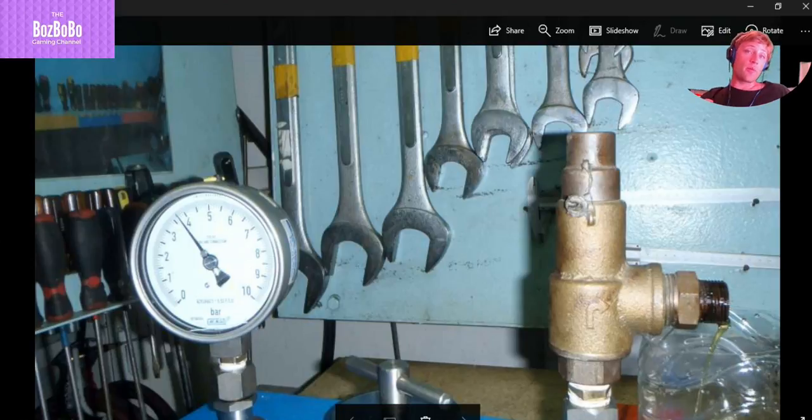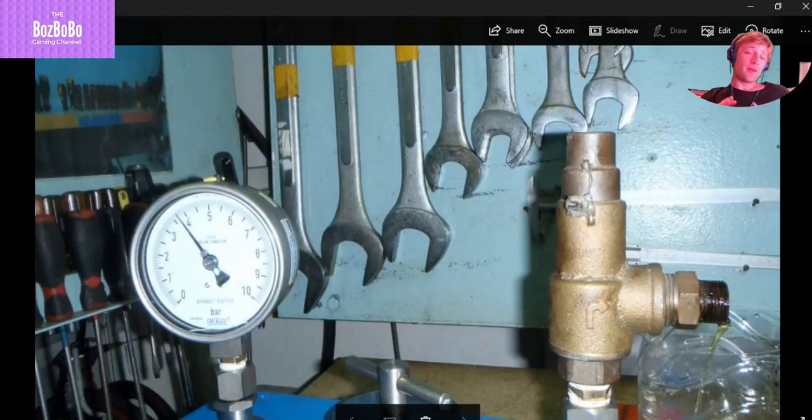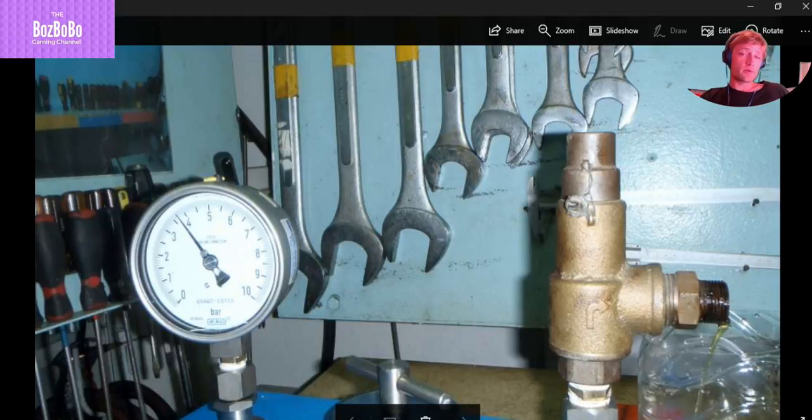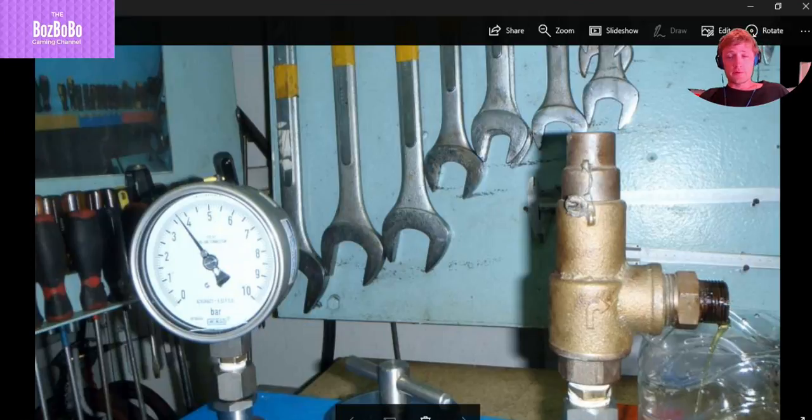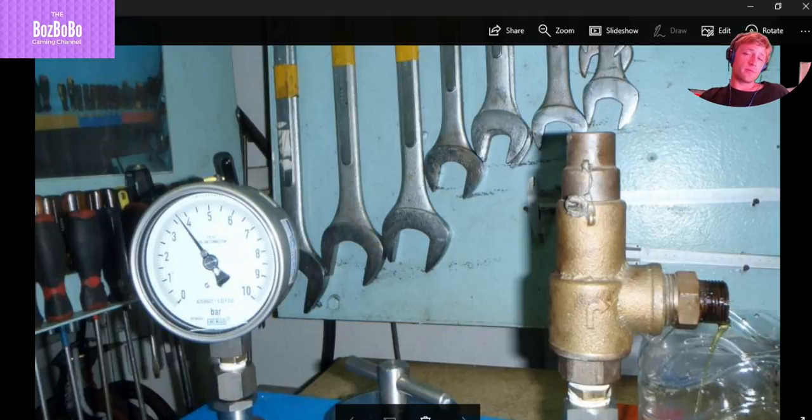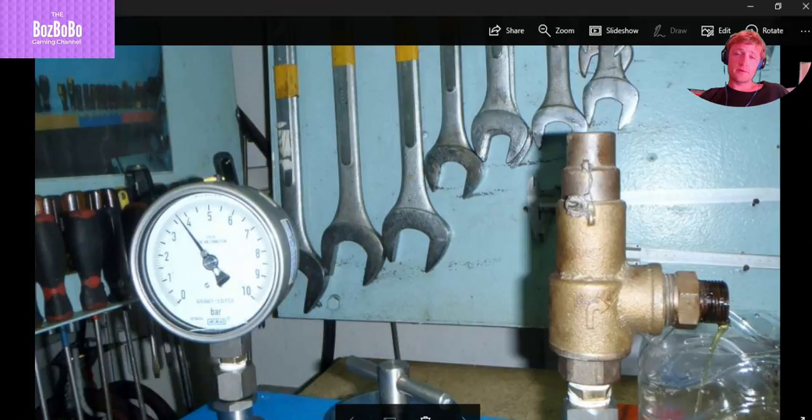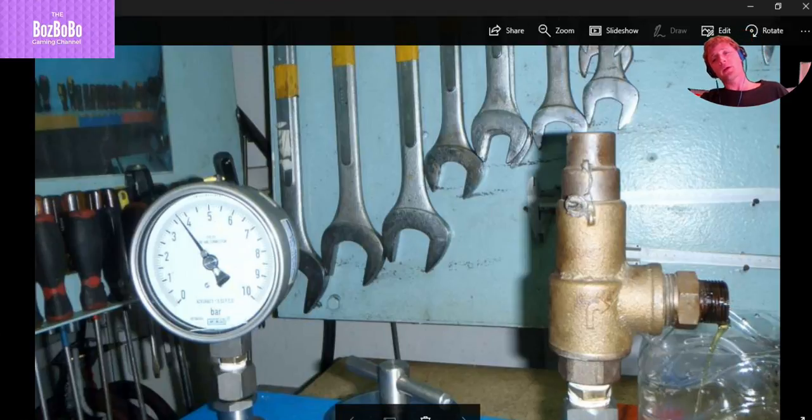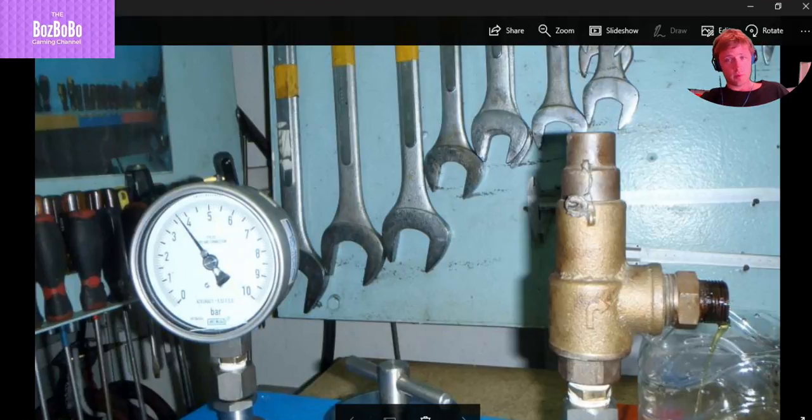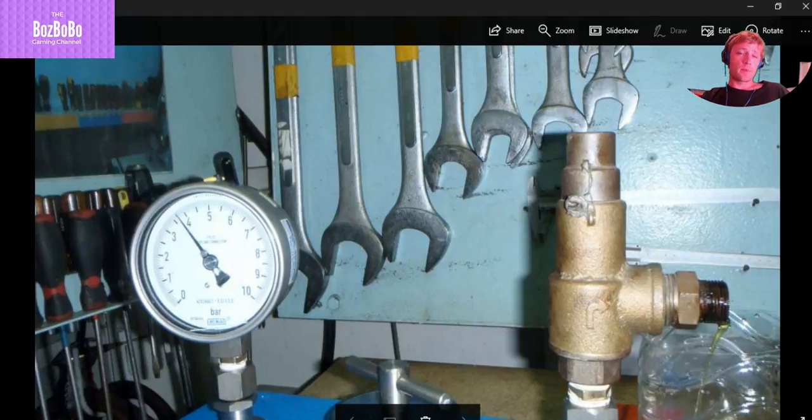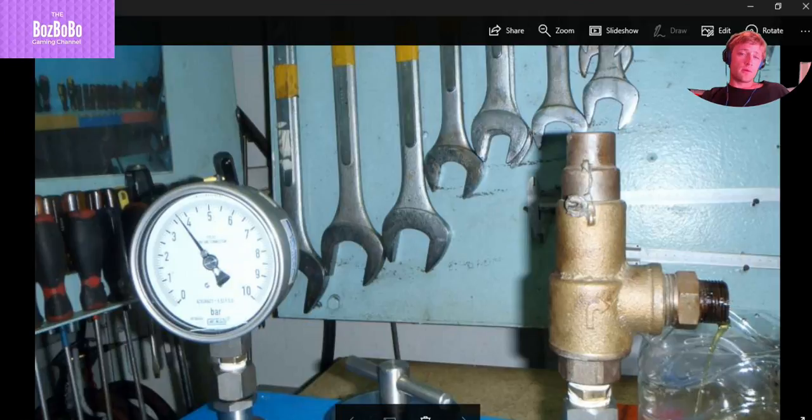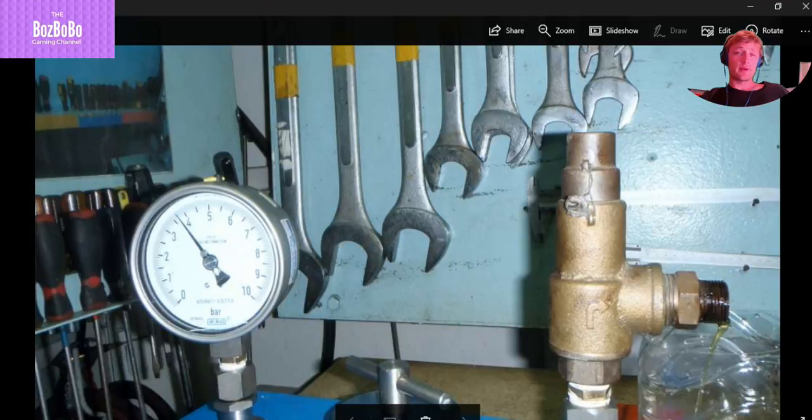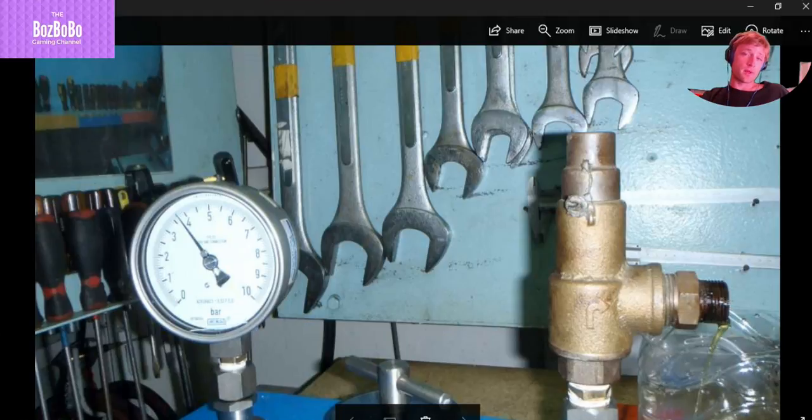And now we compare with the label, the label of manufacture. If for some reason there is different measurements, you can adjust. You just take out this seal and remove this cap, unscrew this cap. And then there is a bolt which you can set with a spanner and then you can test again the pressure.